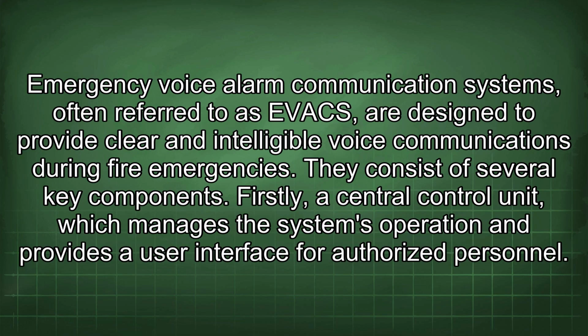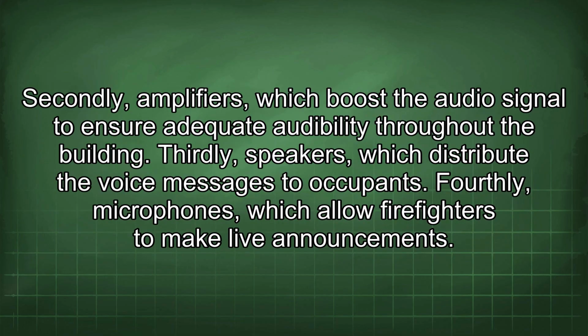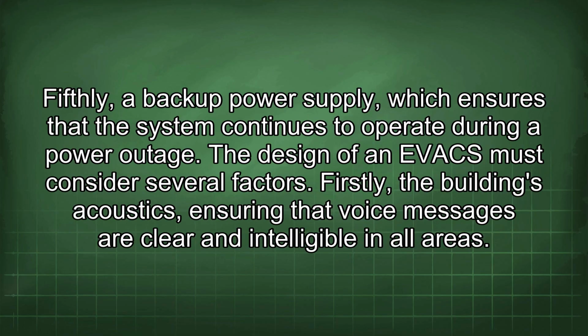Emergency voice alarm communication systems, often referred to as EVACs, are designed to provide clear and intelligible voice communications during fire emergencies. They consist of several key components. Firstly, a central control unit, which manages the system's operation and provides a user interface for authorized personnel. Secondly, amplifiers, which boost the audio signal to ensure adequate audibility throughout the building. Thirdly, speakers, which distribute the voice messages to occupants. Fourthly, microphones, which allow firefighters to make live announcements. Fifthly, a backup power supply, which ensures that the system continues to operate during a power outage.